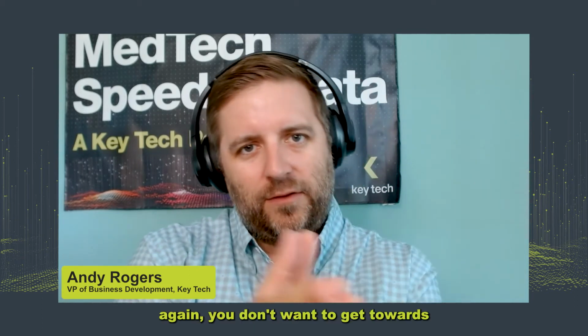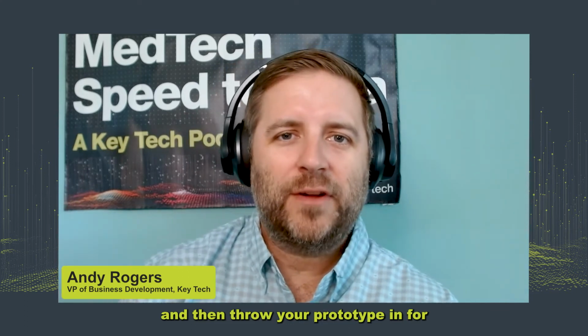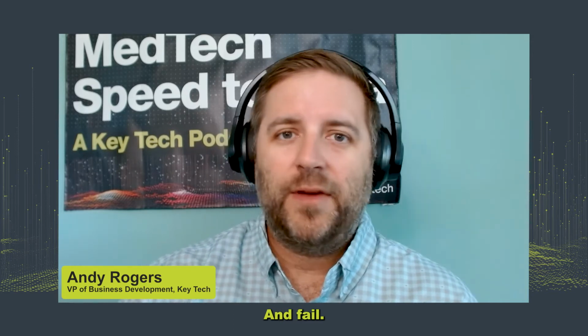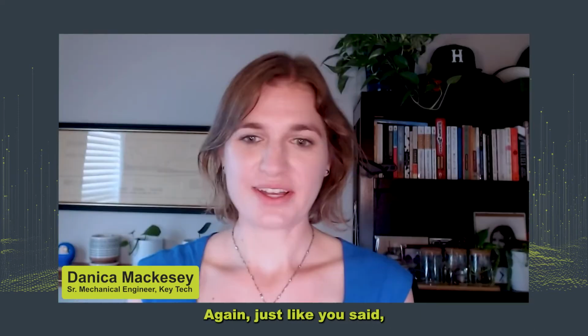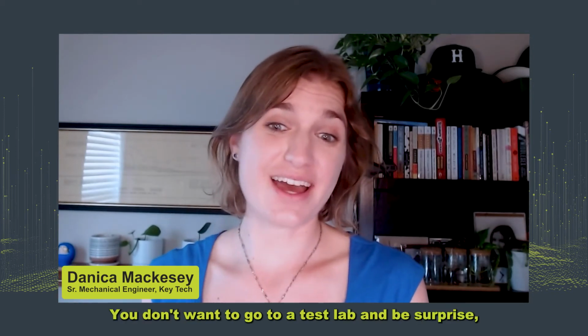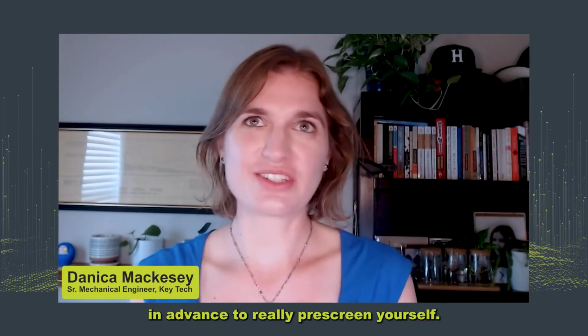Again, you don't want to get towards the end of product development and then throw your prototype in for an initial 60601 evaluation and fail. So Danica, you want to talk a little bit about meeting 60601 requirements? Again, just like you said, you want to consider it early. You don't want to go to a test lab and be surprised. Do whatever you can in advance to really pre-screen yourself.